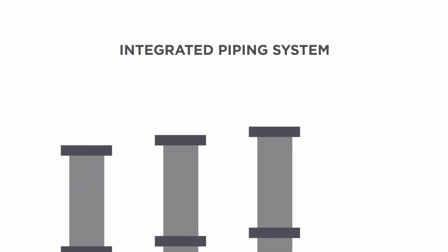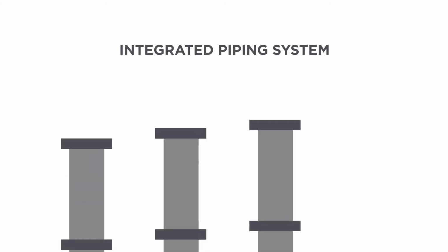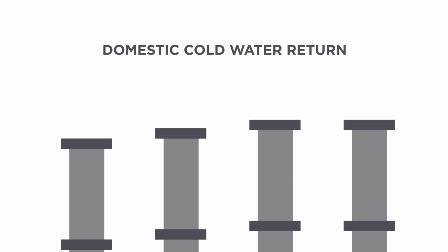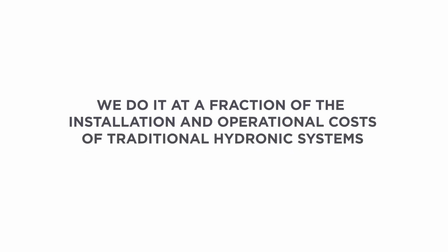The integrated piping system uses the same 3 domestic water pipes every building is required to have, and simply adds one, the domestic cold water return, to give the clients a true 4-pipe heating and cooling solution. And we do it at a fraction of the installation and operational costs of traditional hydronic systems.